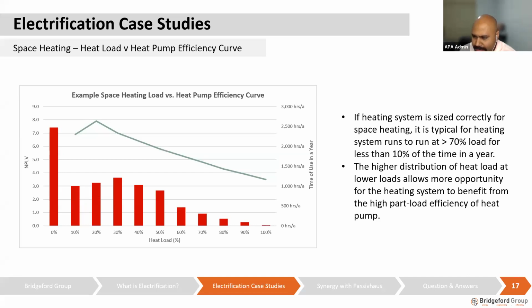How do you size a system for a home in order to run on part load? This is from Paul. This is a question we get asked often, because when we share this knowledge with our clients, they get very excited and say, if the efficiency is so high, why not size up the system so that it only runs at 20% capacity? Well, that's not a very reliable solution, because you would probably have to oversize your system by 3 times, 4 times, or 5 times in order to achieve a really high part load efficiency.